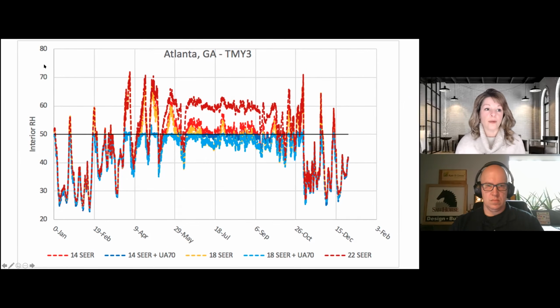And over here we have our relative humidity, so we've got 20 all the way up to 80. And then we have the different times of the year, January to February. And we've got different equipment that we are demonstrating on this graph. So the 14 SEER system is the lighter red. Basically what this is showing us is that 14 SEER system throughout the year on our relative humidity chart. We've got May. Oh, we're way over here. Obviously, we've got high humidity.